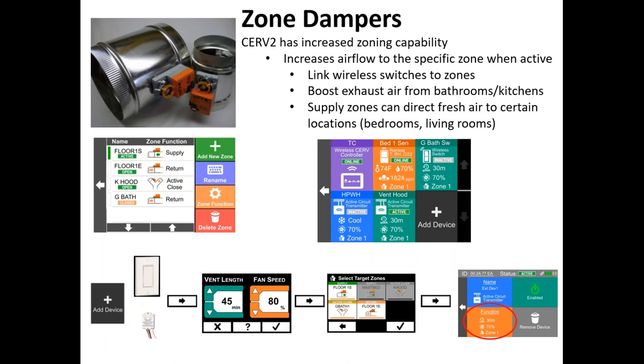Zone dampers can layer on top of these. Once these are configured on the output channel for controlling, you would link these to the different devices. At the bottom it shows configuring a wall switch or a circuit transmitter. You're setting the ventilation time length and fan speed, and then you can select the targeted zones. If you had a master bathroom, a half bath and a kitchen zone, and you link a wall switch to the master bath, whenever it is pressed, it would close down the zones going to the kitchen and half bath.